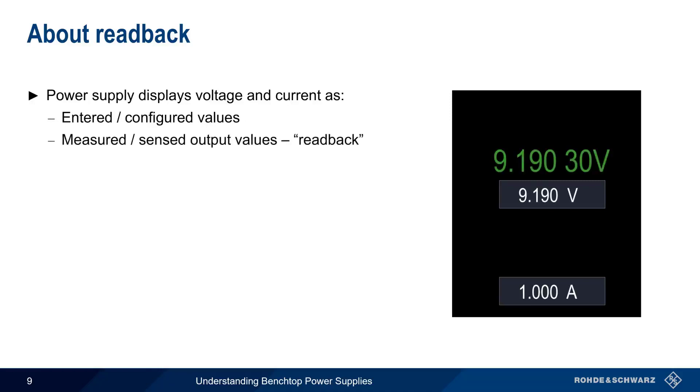Regardless of the output type, many power supplies will show two values for voltage and current. The first set of values are the values entered by the user. The second set of values are the measured or sensed values of what the supply is currently outputting. This function is often called readback. In normal operation, the readback voltage values should be fairly close to the configured value, although later in this presentation, we'll discuss when this might not be the case.